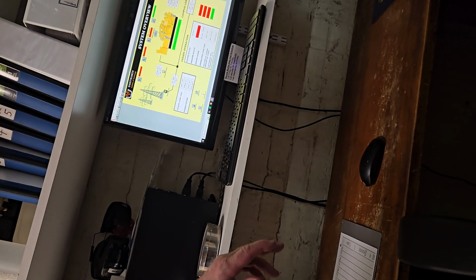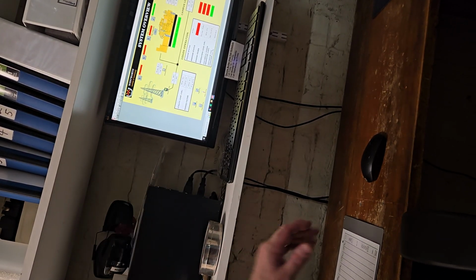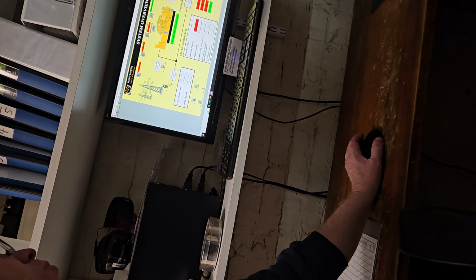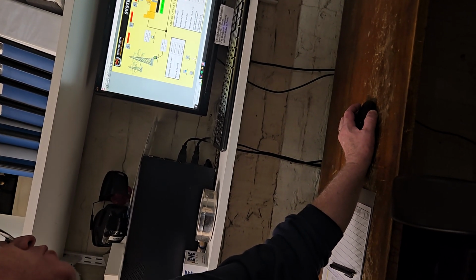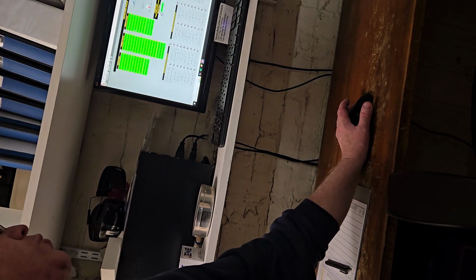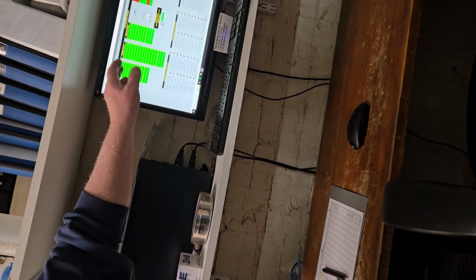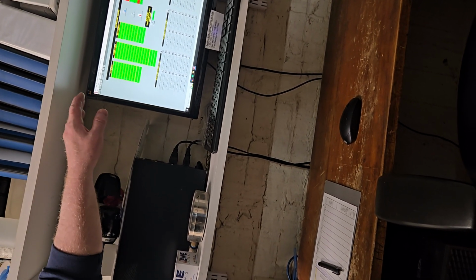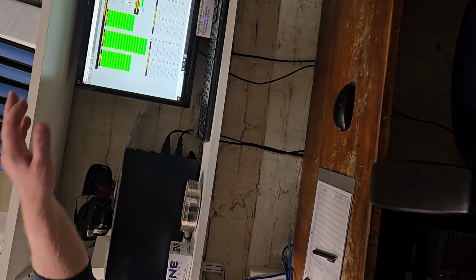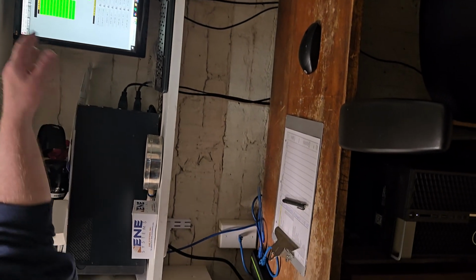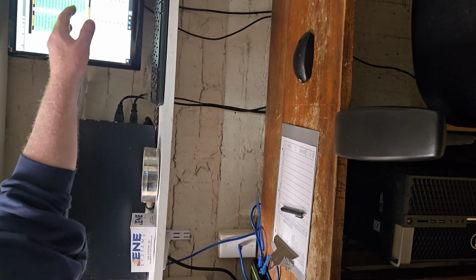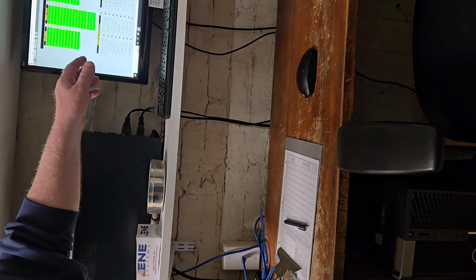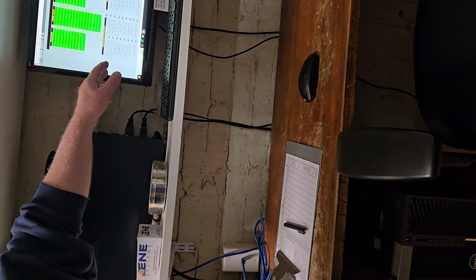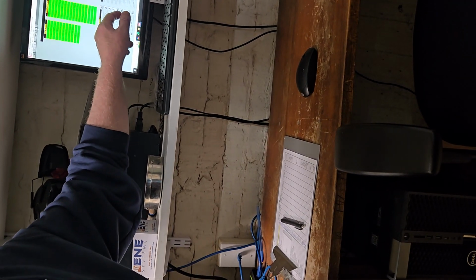It's just a screen we start off in, but a lot of times I'll go down to the engineering screen, which is this screen right here, which you may have seen before. This screen tells us any alarms that come in, helps us troubleshoot and diagnose, and also tells us a lot about temperature and pressure -- steam pressure, the pounds per hour. I told you it's around 16, right now it's 1638.